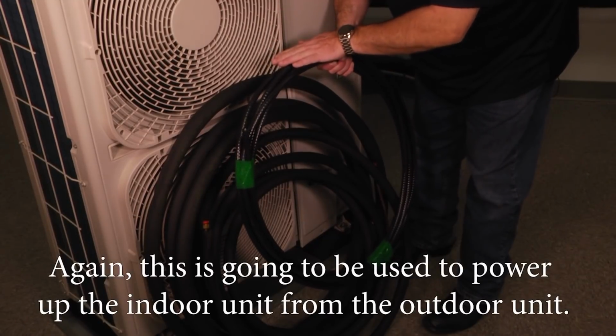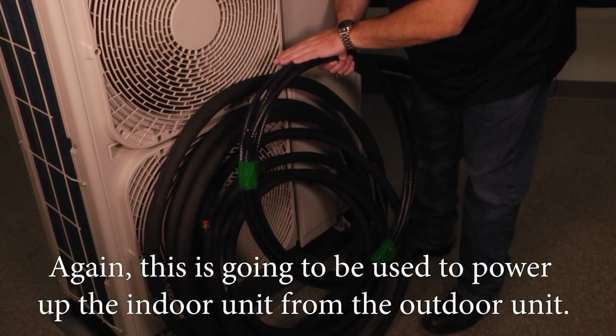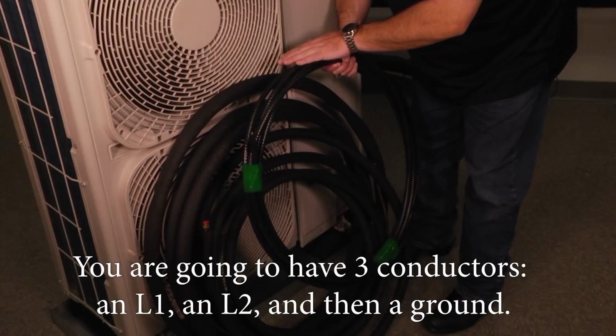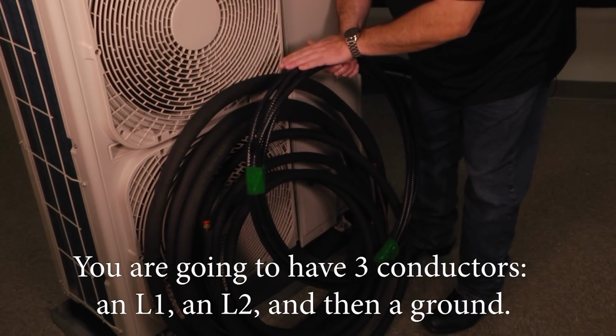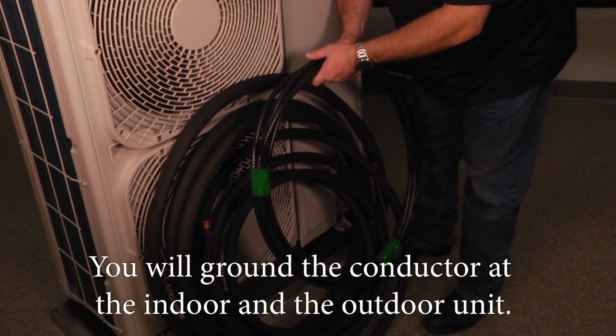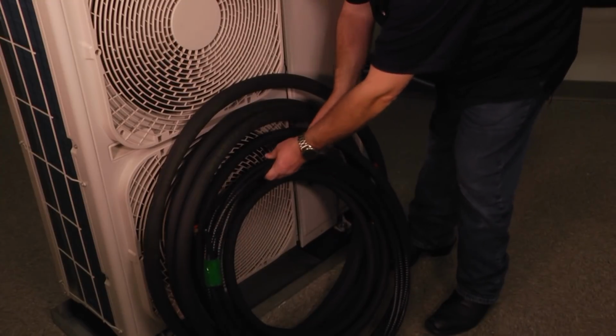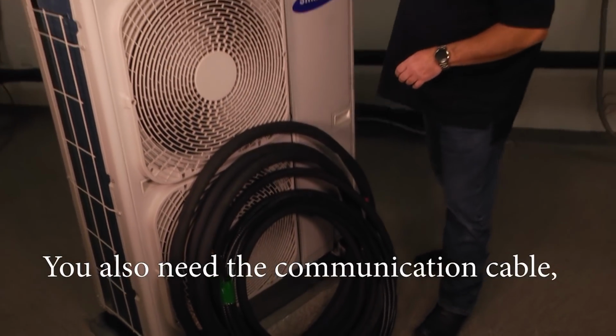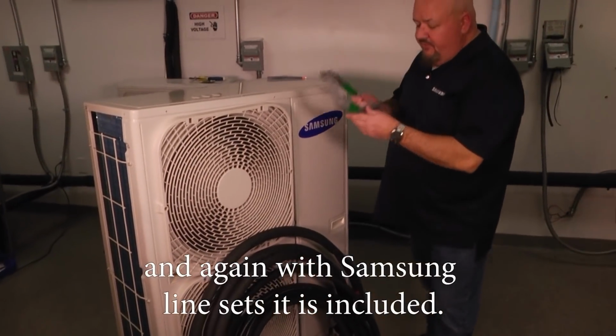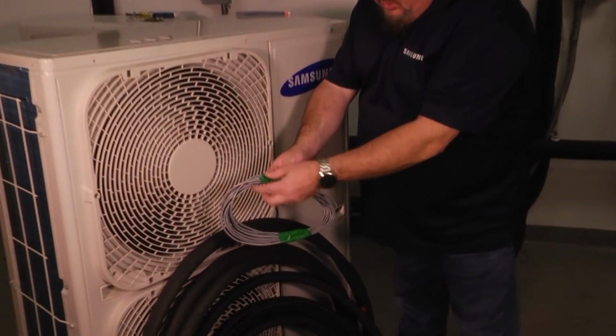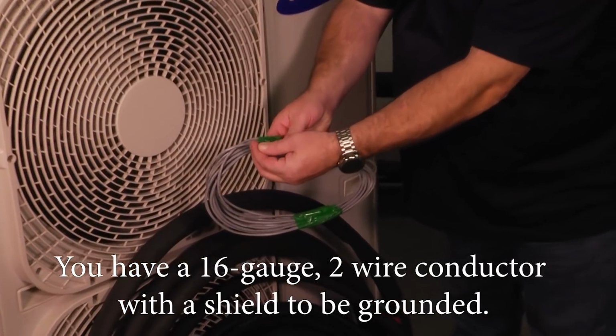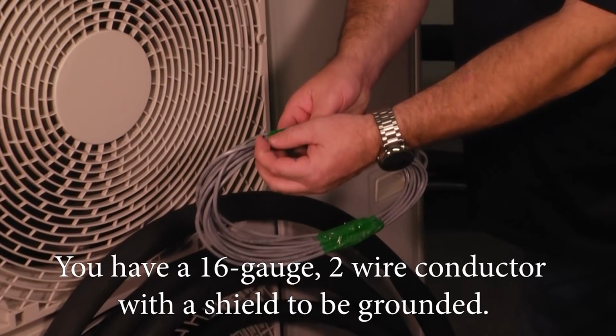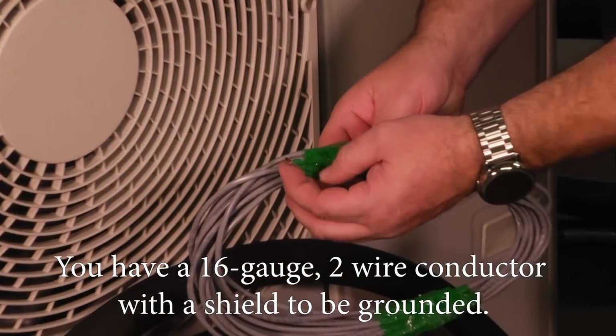Again, this is going to be used to power up the indoor unit from the outdoor unit. You're going to have 3 conductors, an L1, an L2, and then a ground. You will ground the conductor at the indoor and the outdoor unit. You also need the communication cable, and again with Samsung line sets, it's included. You have a 16 gauge 2-wire conductor with a shield to be grounded. This wire comes with the line set.